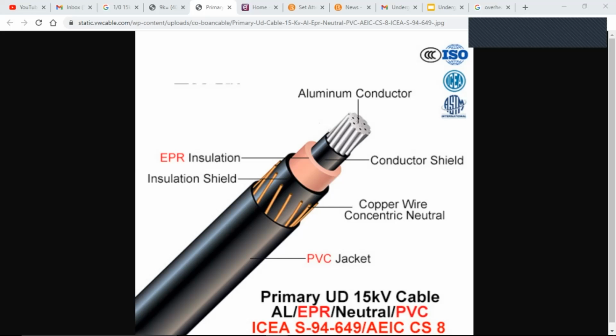All right, so your concentric neutral, and then the PVC jacket. Now you need to look out here. It's the assumption that this outer jacket is insulated. Is it? It's not, sorry to say. It's just a protective jacket that goes around the neutrals, one, so the neutrals don't corrode as easily in highly acidic soil, and two, because sometimes you're going to push a shovel into it, or something's going to dig into it, not with great force, and you've got some protection going on here. It is not to be considered an insulated covering on the conductor.